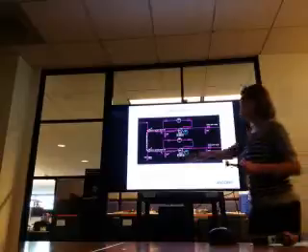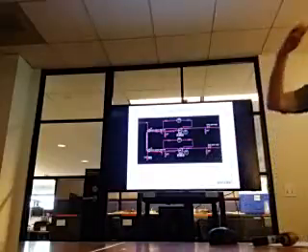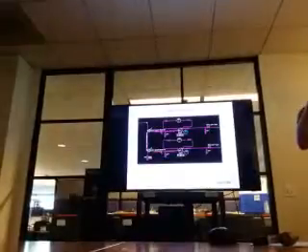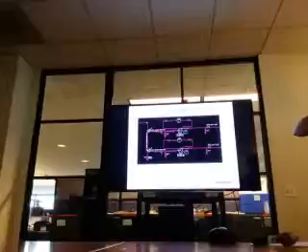Block valves are known as isolation valves, and just like we were talking about here, we have them at drains, we have them around pieces of equipment if you need to service them, and around instrumentation. So this here is a gate valve. It's blocking the flow. When we lower the gate down into the seat, you can't go through it anymore. It's a multi-turn valve. The nice thing about gate valves is they come in small sizes and large sizes. If you had to pick a service where you're going to use a gate valve a lot, it's steam condensate. It's used in others, but you probably wouldn't use a brass one in steam and steam condensate, but this is a gate valve. It's just isolating the flow, blocking the flow from going down.